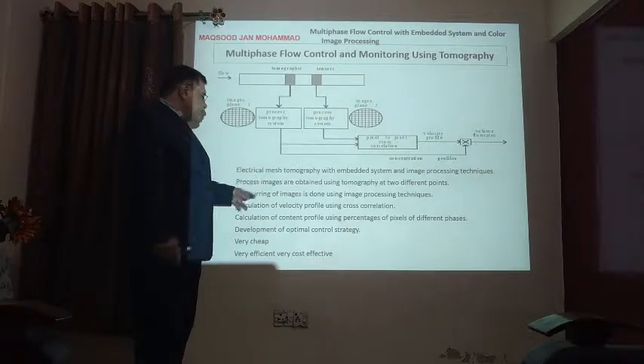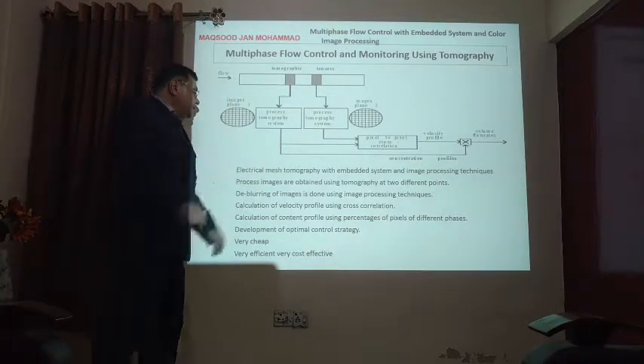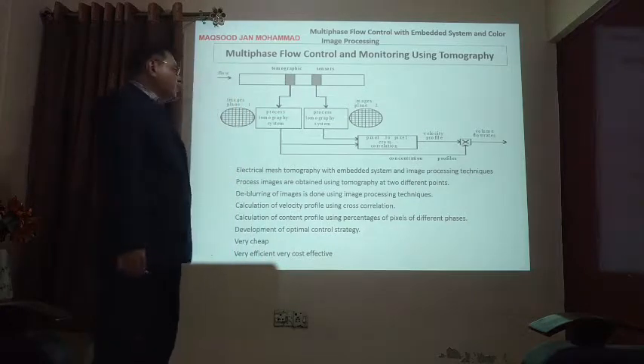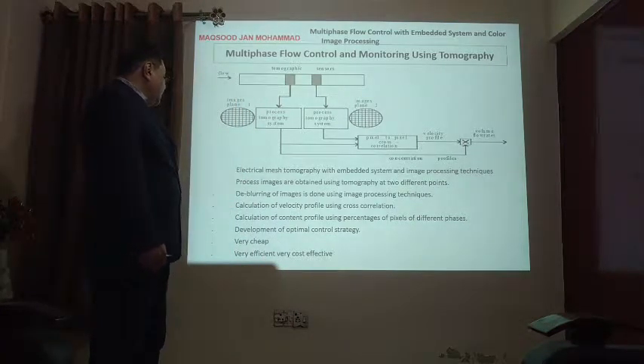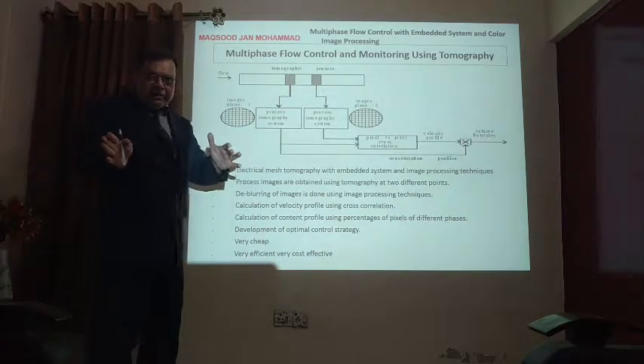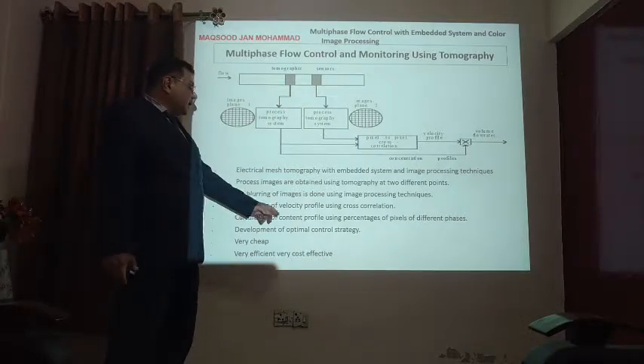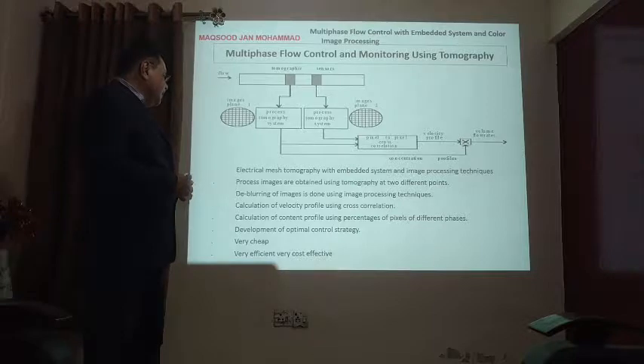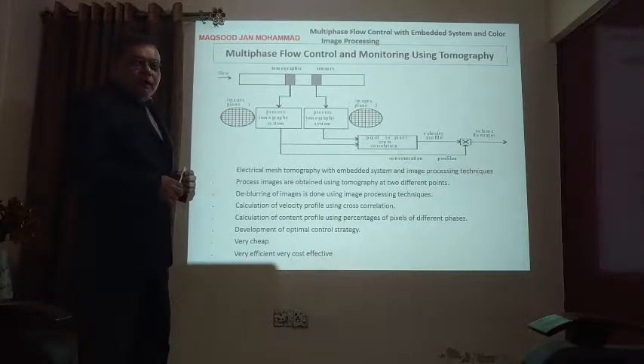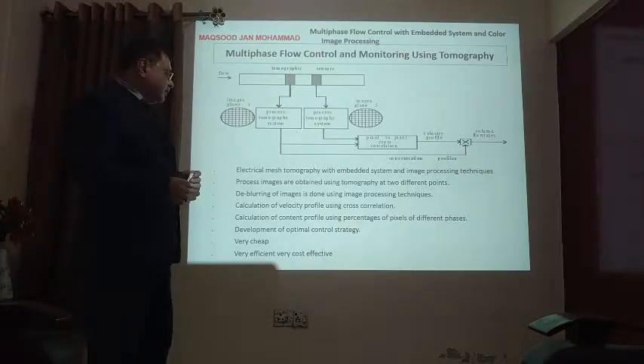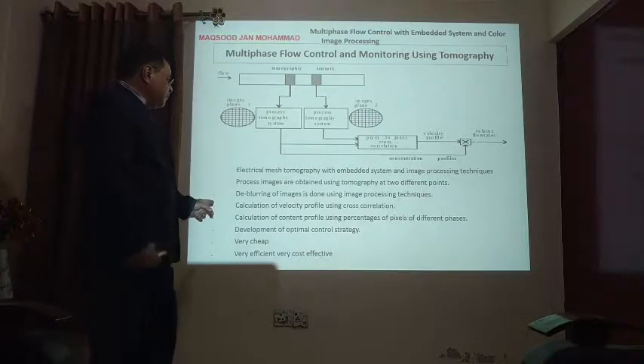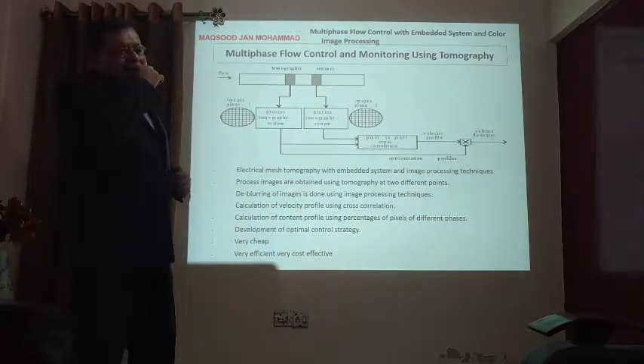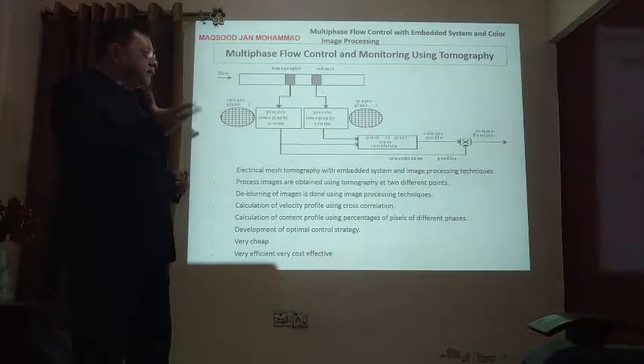At two sensor positions, we calculate the velocity profile using cross-correlation. Cross-correlation between the two images allows calculation of the content profile using percentages of pixels of different phases. We can find out what percentage of oil, gas, and water is present. This supports the development of an optimal control strategy for the oil and gas industry.